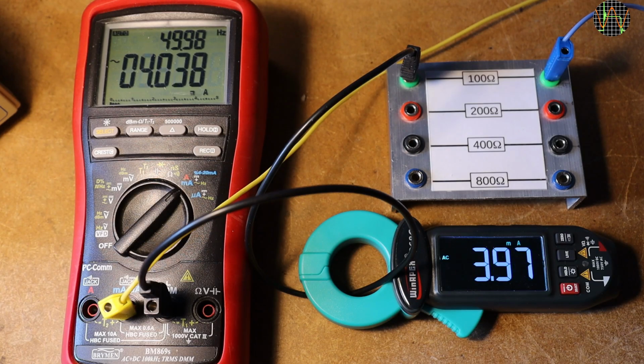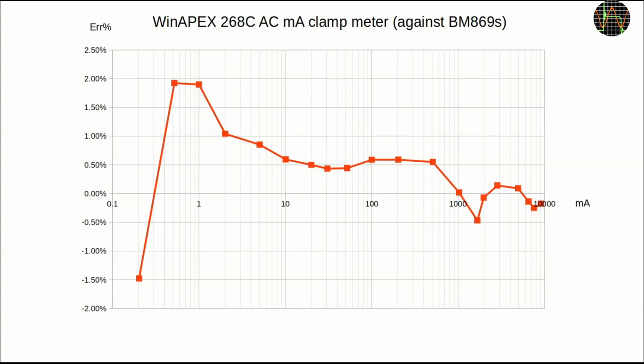Since the main purpose of the 268C is to measure leakage current, I decided to spend some time on that function. As a start, I measure the accuracy of the very low currents that we are dealing with here, and I must say the 268C is surprisingly good at that. I'm using a signal generator for this, hence the current limiting resistor of 100 ohms. For higher currents I use a mains transformer. The results are in this chart, tracing the performance from 200 microamps to 10 amps against the BM869S, which of course has its own accuracy spec.